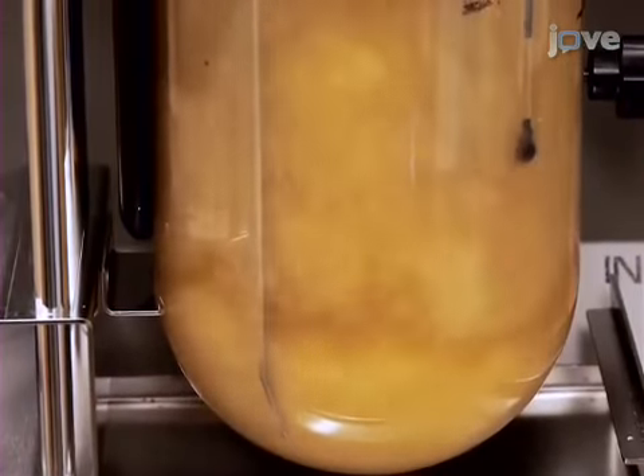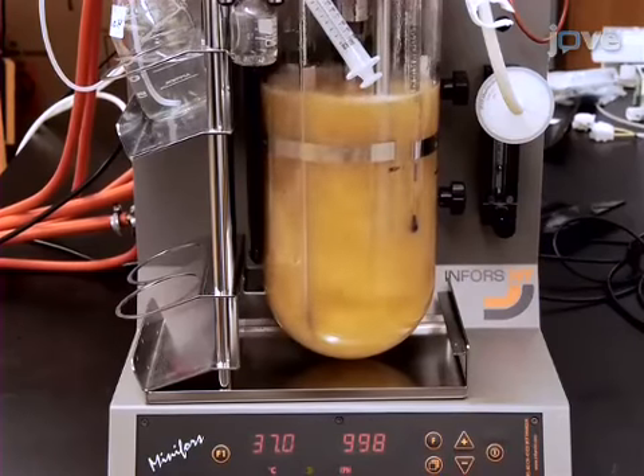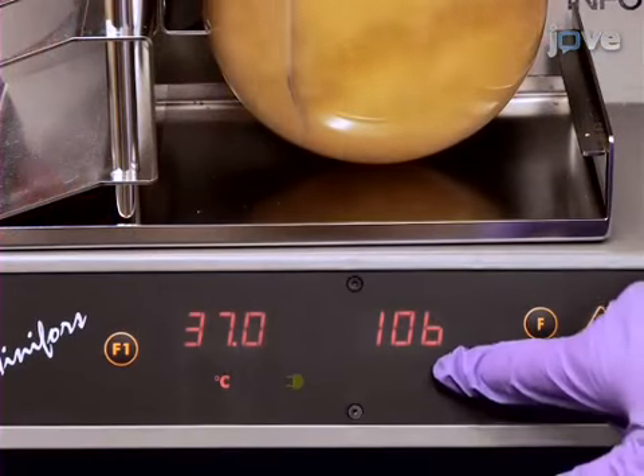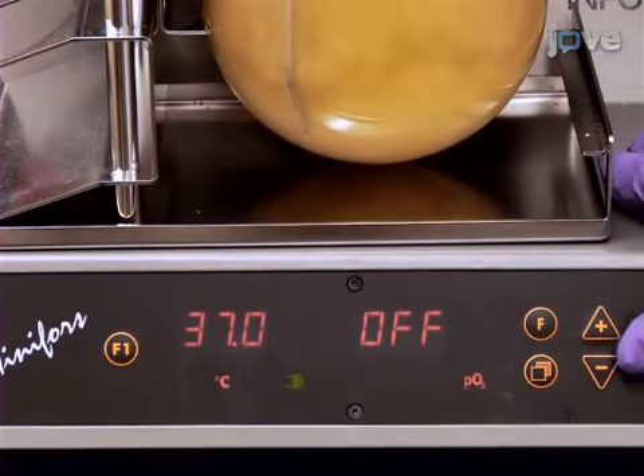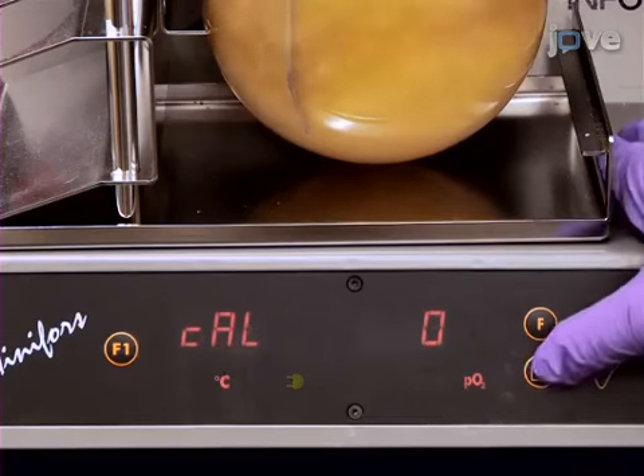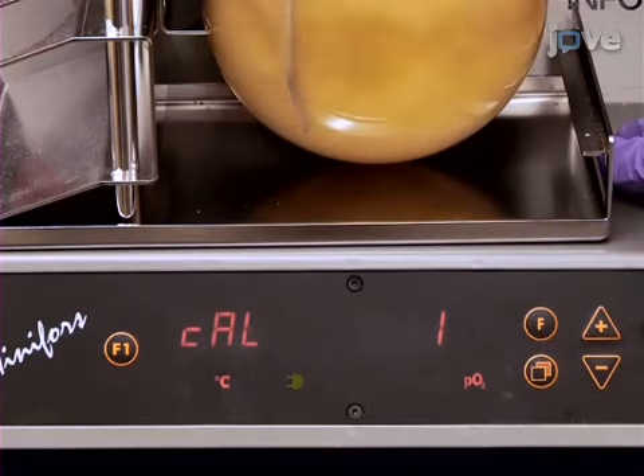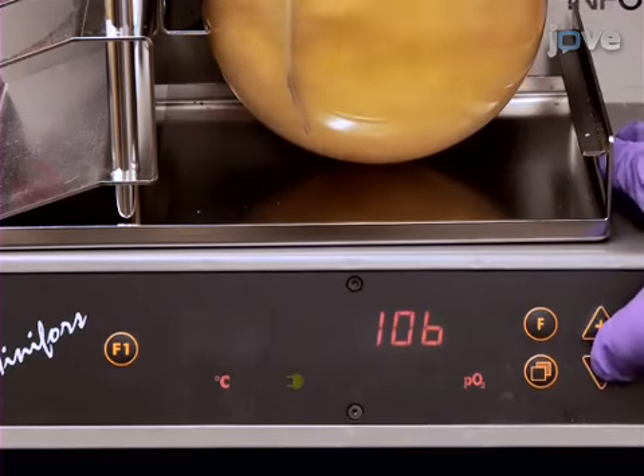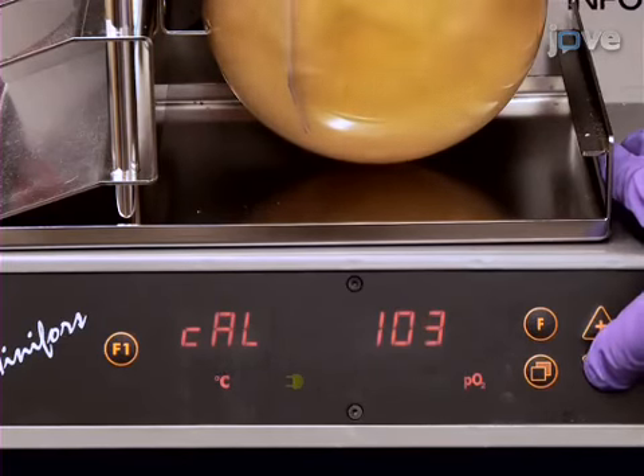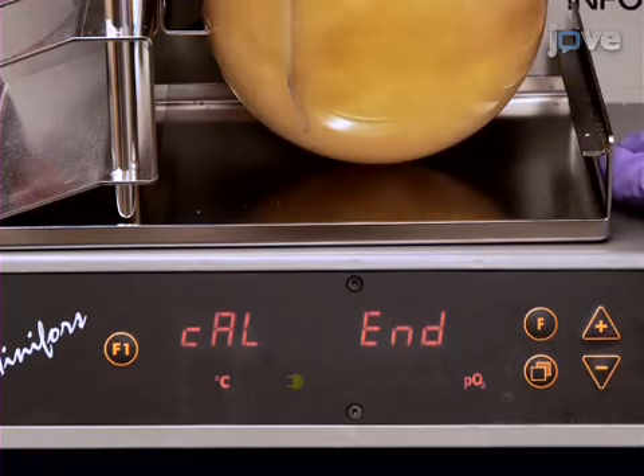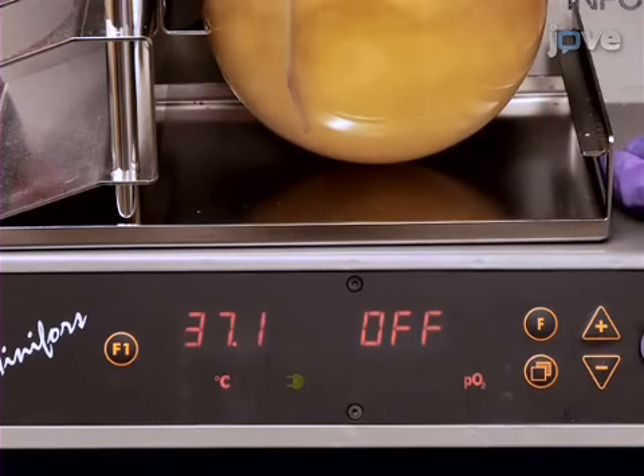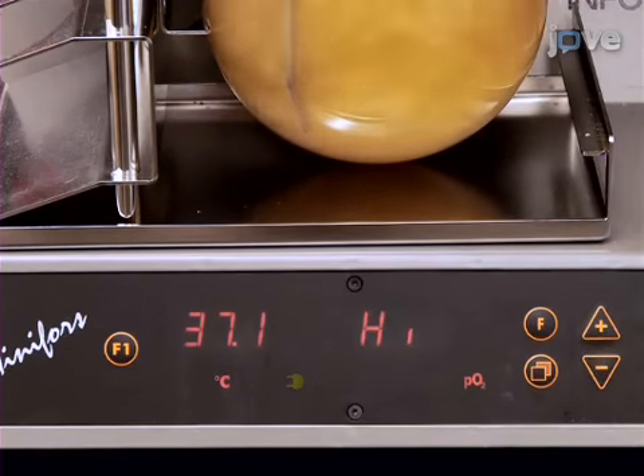Ensure that the oxygen probe is polarized properly to display proper values. After 2 hours, scroll to the oxygen parameter. Use the menu button to select the calibrate function and select the 1-point calibration. After 15 minutes, use the cursors to set the value to 100 and press Enter. This will calibrate the oxygen saturation.